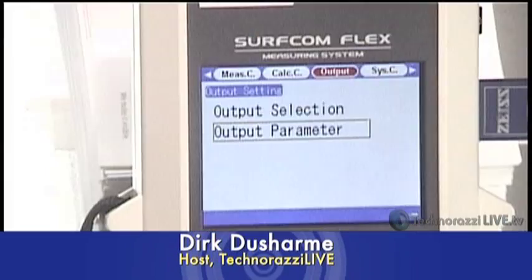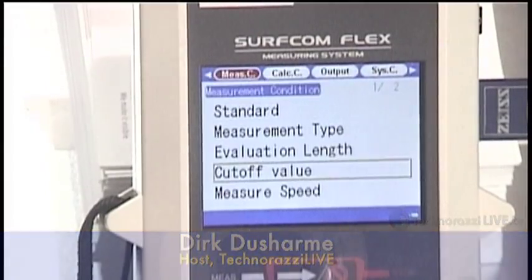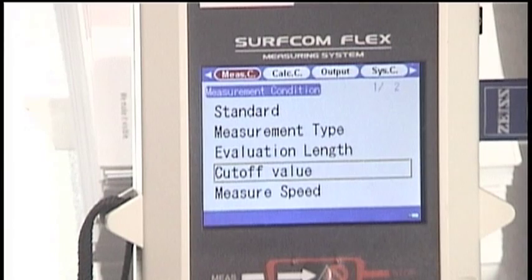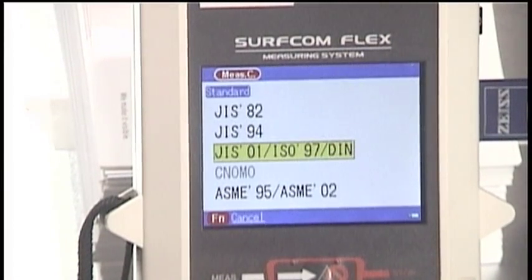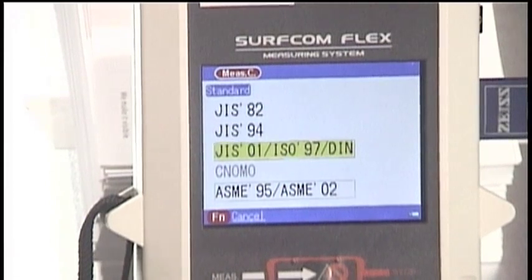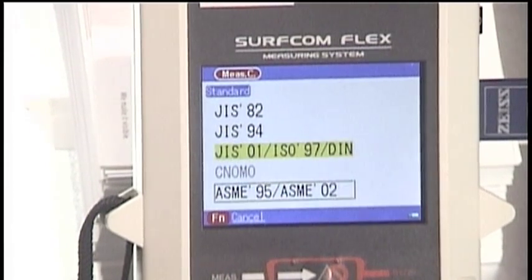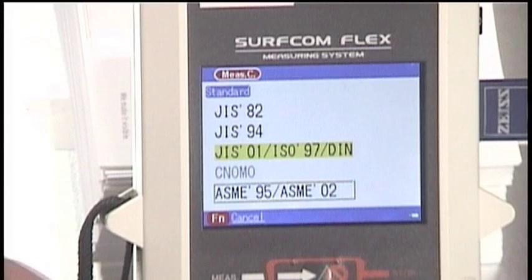Yeah, definitely. So depending on what your print calls out for, you can have the Surfcom Flex measure to those standards. And if we take a look at the screen here, we see all the different standards that are available on the Surfcom Flex. Right now I was using the ISO 97. Let's say I wanted to measure per the ASME standard. I can change it to that standard and then recalculate my data.